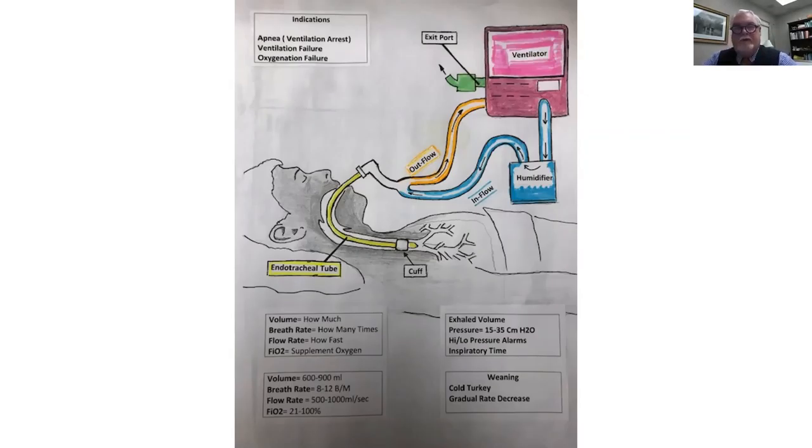So there's going to be a monitor on that machine that has the amount of air that leaves the machine and the amount of air on exhalation that returns to the machine. And it should make sense that those match. So if you got 700 going in, you ought to have 700 going out. Then there's also alarms on the machine that will, for example, if you have 700 going in, and we only have 600 going out, then we got a problem. We've got a leak somewhere. It could be in the endotracheal tube where the cuff isn't inflated enough. It could be a leak in the patient's lung, which is a lot more serious. Or there could be a leak in the tubing somewhere. So that's essentially how the machine works.